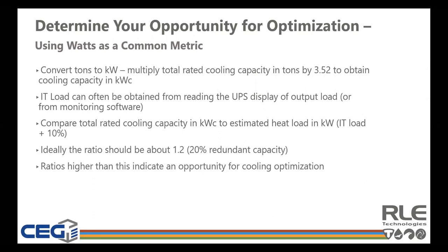Even today, and this has been going on for a while, we've all heard this, we still see data centers that are 2 times, 3 times, or even more overcooled. So there's still a big opportunity, and you can self-assess your own data center by doing those 2 high-level comparisons. Now I'm going to hand it back off to Tim, who's going to go through some specifics about the floor panels and their role in proper airflow management.